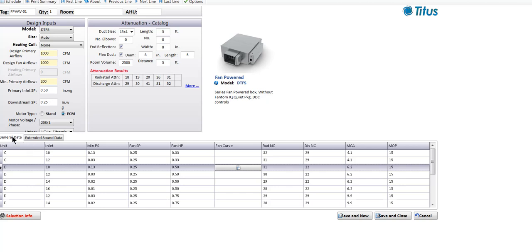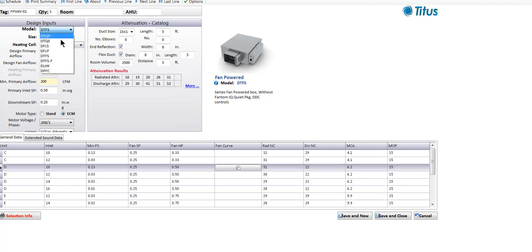We'll go with unit size D with a 10 inch inlet. Looking at the sound data, this unit has a radiated sound level of NC31 and a discharge sound level of NC22 — that looks really pretty quiet. Now if we had a sound critical situation like a conference room and didn't want to select an NC31 box to go over an NC30 conference room, we have another option: a quiet version called the DTFS-F.